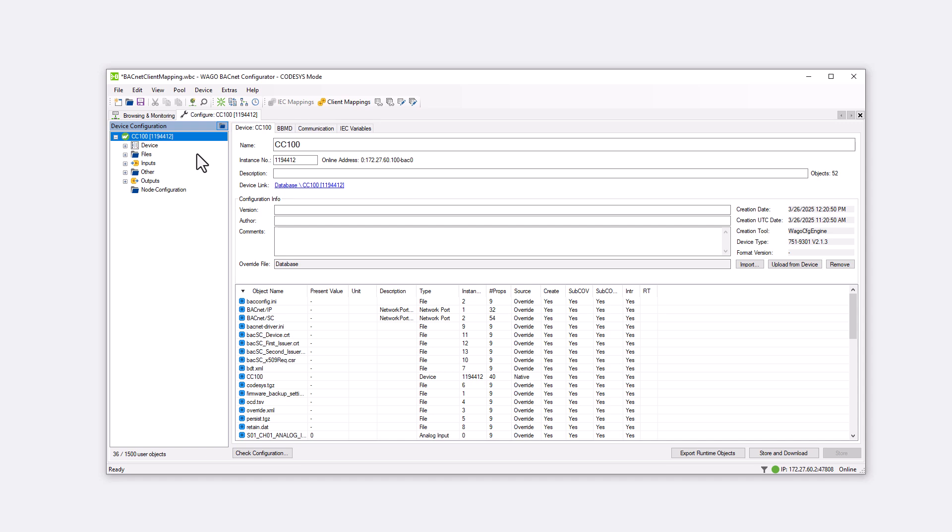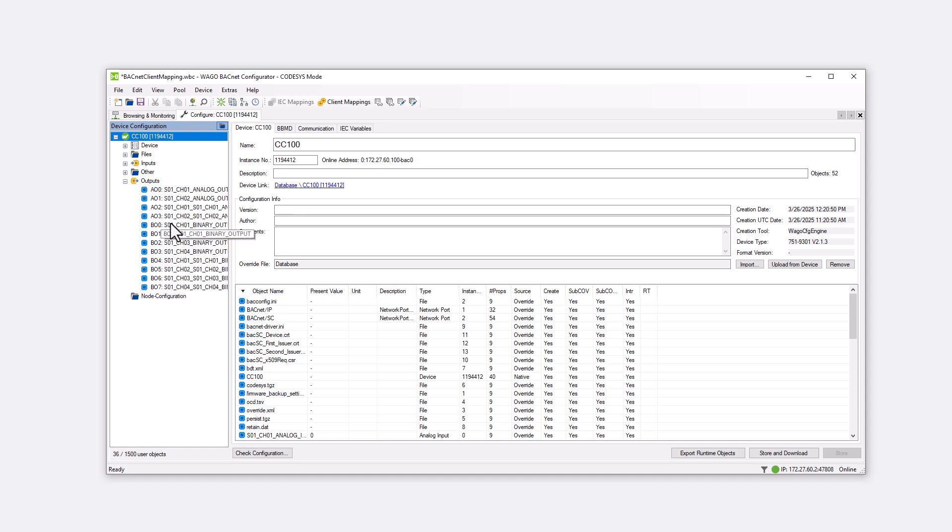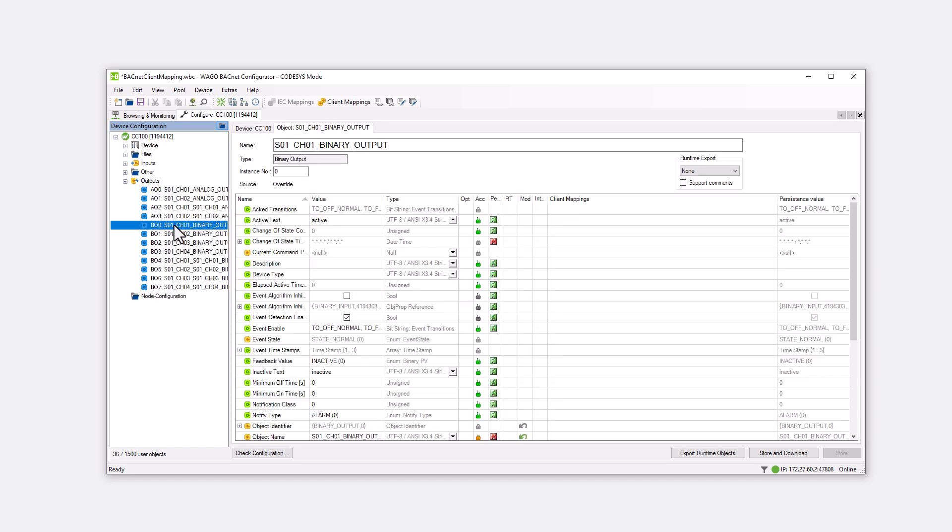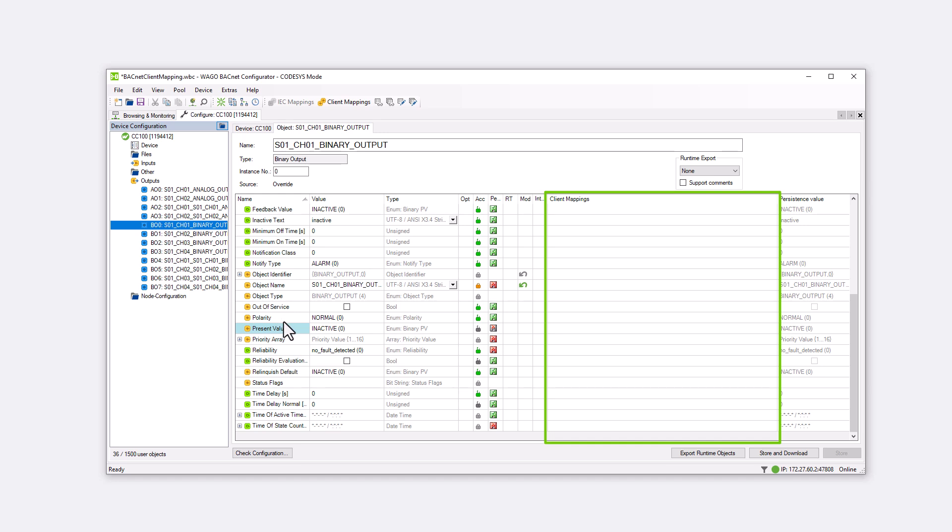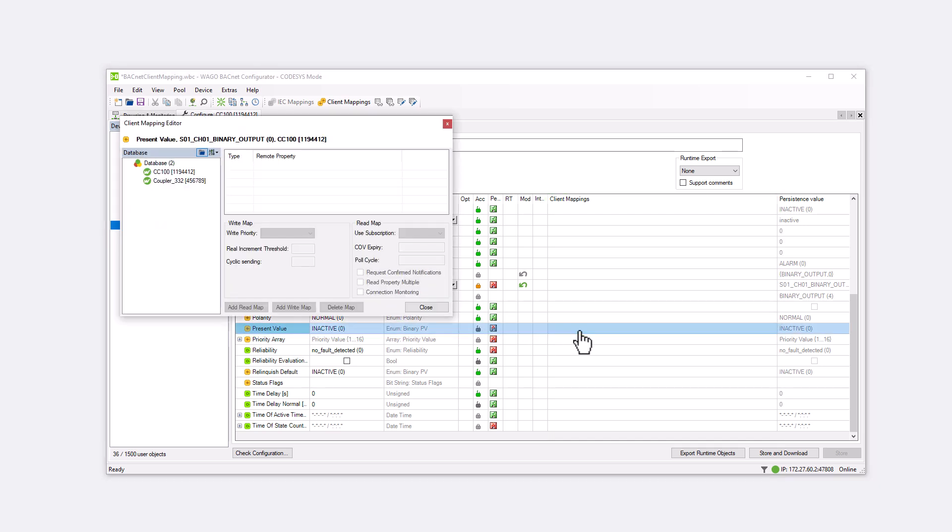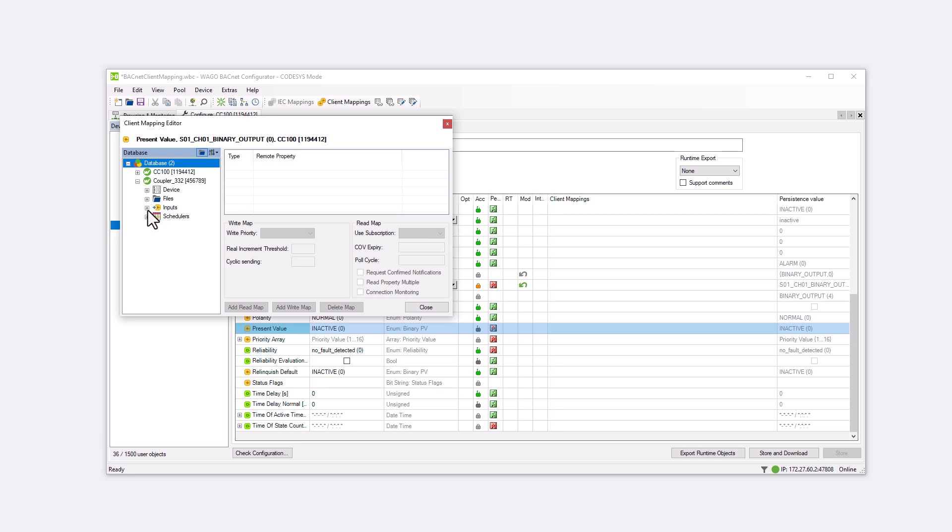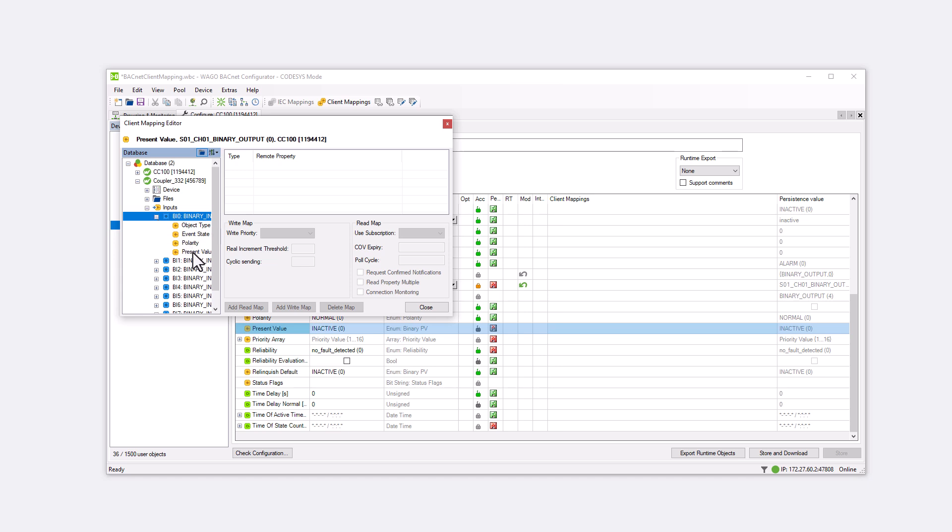Since we want to switch the DO1 on the CC100, go to Outputs, open the tree with the plus sign and select the first binary output. In the table on the right, we find the column Client Mappings. Clicking in the Present Value field in the Client Mappings column opens the Client Mapping Editor. Here we map the output of the CC100 to the input of the coupler. To do this, open the inputs of the coupler and find the needed present value in the binary input 0 tree. With the Add Read Map button, we link the two properties using the Read function.